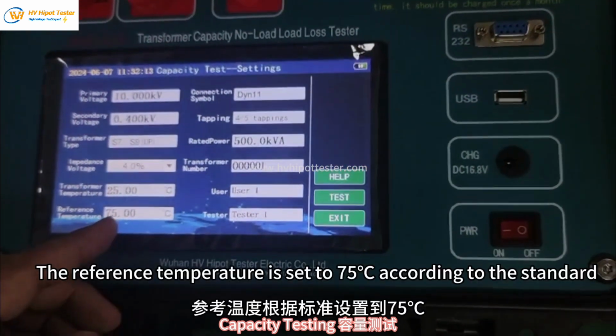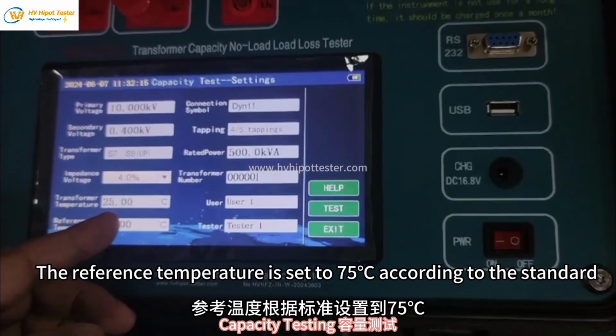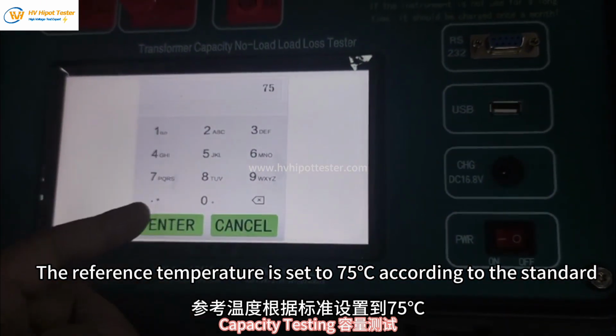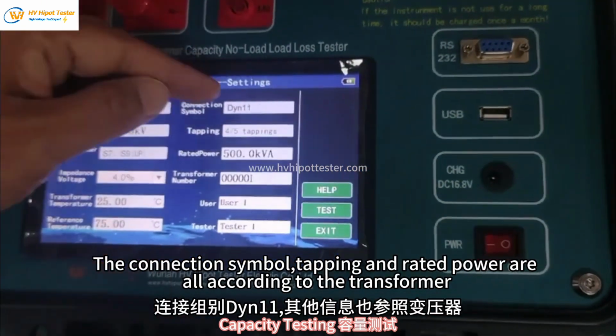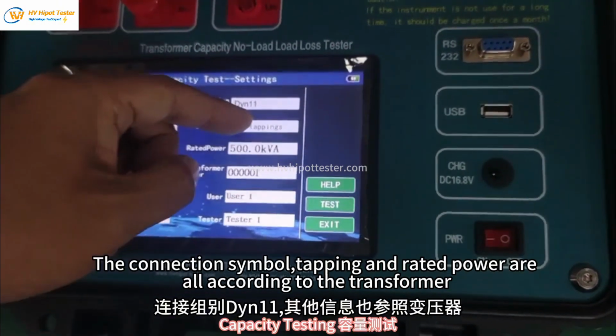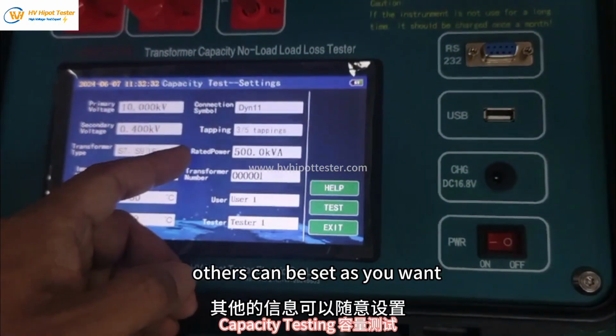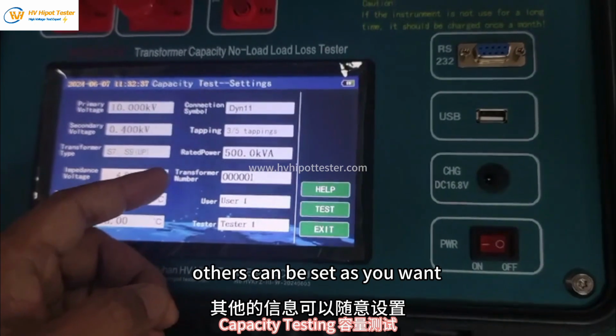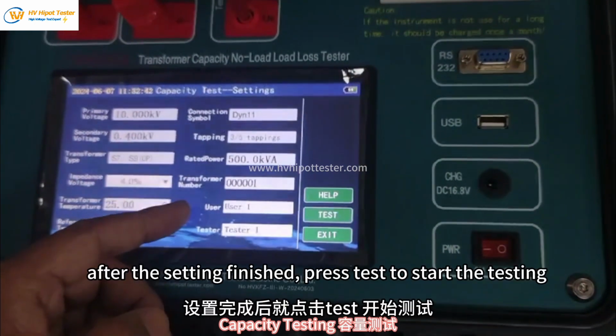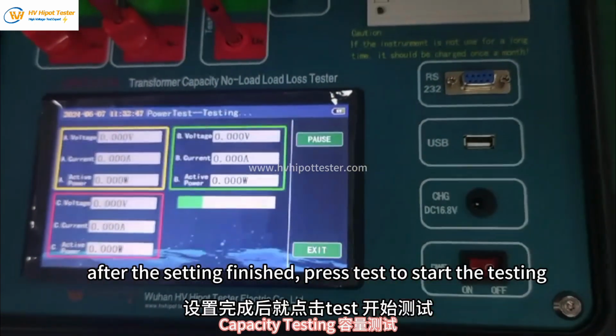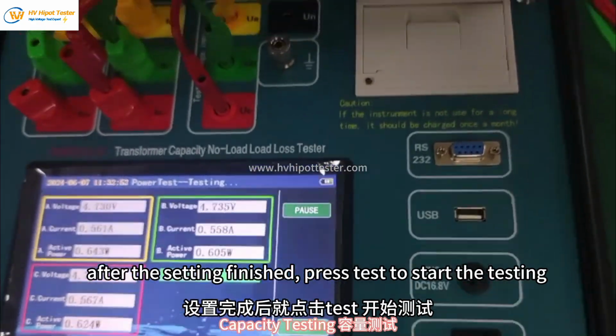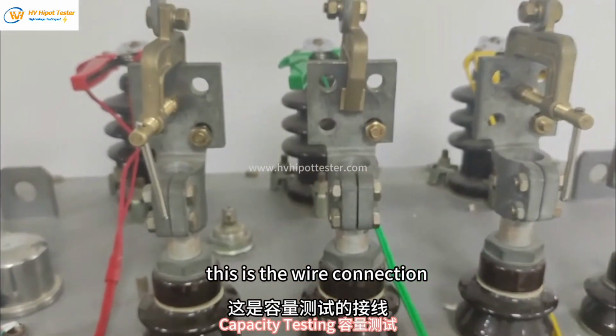The reference temperature is set to 75 degrees according to the standard. The connection symbol, tapping and rated power are all according to the transformer. Others can be set as you want. After the setting is finished, press test to start the testing. This is the wire connection.